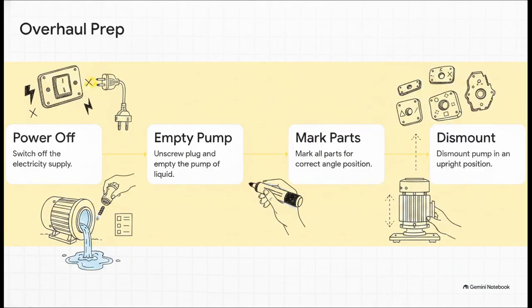So, when you finally hit that 6,000-hour mark and it's time for the big overhaul, safety and precision are literally priority number one. Step one, obviously, switch off the electricity. Step two, unscrew the plug and completely empty the pump of liquid. Step three is vital for when you have to put it back together. Mark all the parts to ensure they go back in their exact correct angle and position. And finally, step four, dismount the pump in an upright position.